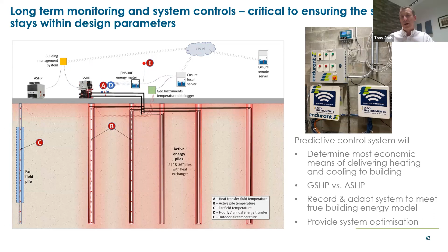Our instrumentation panel here will be able to tell the heat pumps on the roof, you can have heating or you can have cooling. It'll be sending the signal, and there's an algorithm in the controls on the rooftop equipment, so that there are times of the year where the air temperature is perhaps more energy efficient to use for cooling or heating than the ground. So the algorithm within the control system will send a signal to the heat pumps to operate in air source heat pump mode. Then as the temperature increases or decreases during the day, the ground source heat pump system will become more energy efficient, so it'll switch to the ground source heat pump system. It's about providing long-term management and making sure the ground isn't overheating or overcooling over time.